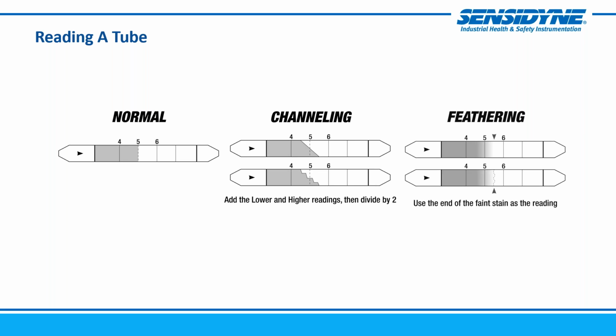Once you complete the sample and you're ready to read the tube, again, remove it from the pump, and look down at the scale. Ideally, you'll see a normal stain change where it's right even with a specific range mark. However, it's not uncommon that some channeling may occur, and this could be a slanted angle across the tube. If this occurs, you would add the lower and higher readings and divide that in half. So in this example, you see that it goes from almost 4.5 to 5.5. You would add those together and divide by 2, and that's where you get an average of 5.